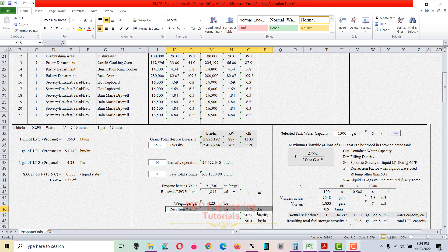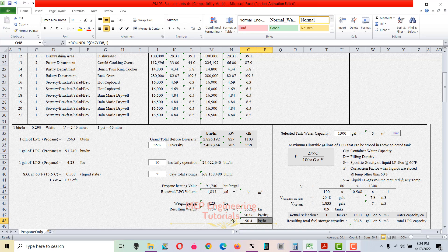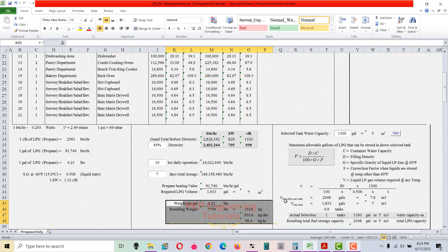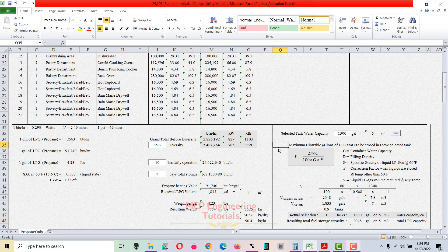This weight is for 7 days of storage. Dividing by 7 gives 503 kg per day. Dividing further by 10 hours of daily operation gives 50.4 kg per hour as the LPG requirement.